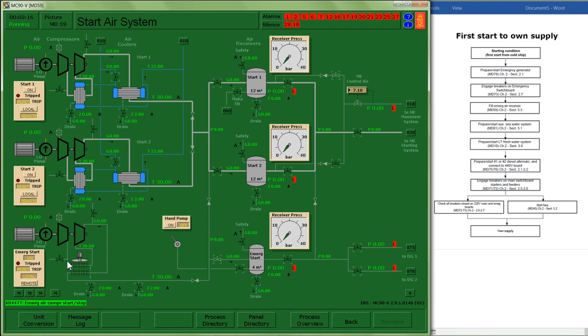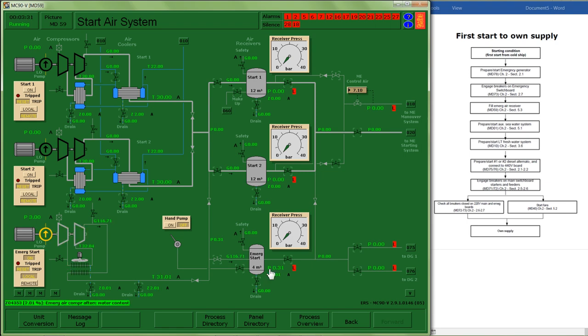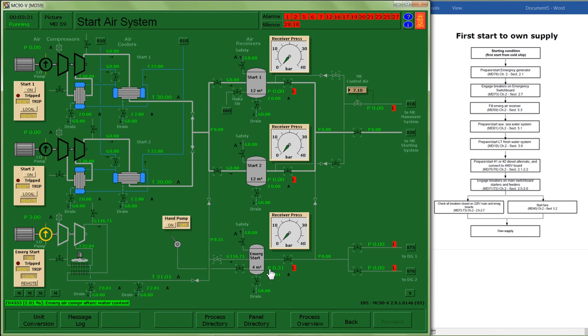I'm going to monitor to make sure that I don't have any leakage through any drains that are open, that I don't have any significant water accumulation, and that I have a pathway to my emergency receiver and it is building pressure. I'm going to complete my pathway to my diesel generators. Maximum pressure is about 30. I'll need at least 15 bar to be able to start the diesel generators.